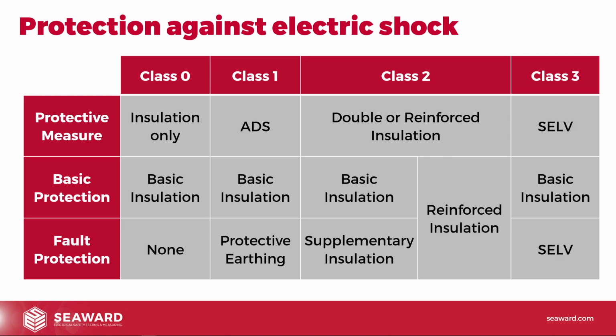So that gives you a good breakdown of how the protective measures are distributed across the various classes and how the basic protection and the fault protection is carried out. Now obviously this stands us in good stead for when we go on to do the inspection and testing, because we know what we have got to inspect, what we have got to test. We've got to check that the insulation does what it's meant to do, the basic protection, and in the case of Class 1 equipment, that the protective earthing is doing its job as well. So having a good understanding of the protective measures gives us a very good understanding for the tests that we need to carry out later on in this series.